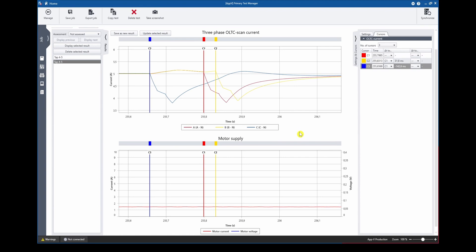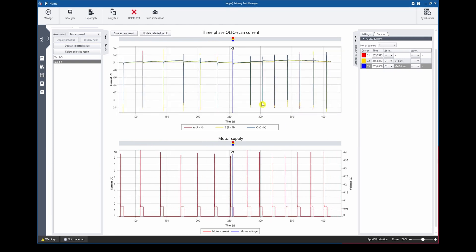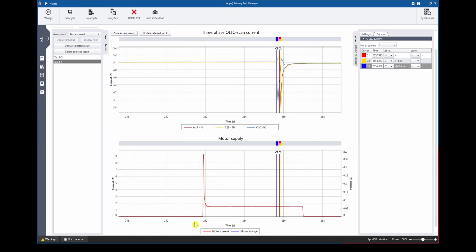Similar to the dynamic current curves we can also analyze the motor supply currents. So if we zoom out again to see the whole tap switch operation range we can see that all motor current activity has been recorded at the bottom diagram and if we were to zoom in for example on one of the curves we can see the motor supply current and now we can use again the cursors to measure out the timings of the motor supply current.